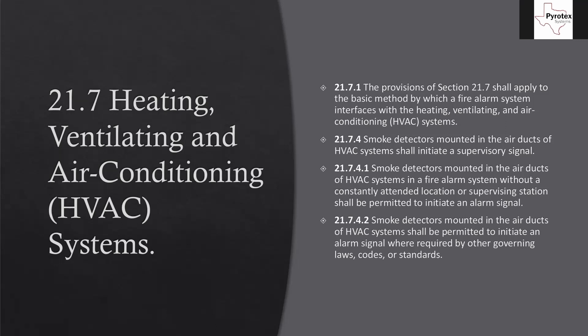The building in question is monitored by a central station over the phone line, so supervisory is still the right way to go. The second allowance: smoke detectors mounted in air ducts shall be permitted to initiate an alarm signal where required by other governing laws, codes, or standards. The local fire marshal for that building had not issued any requirement for the duct detector to initiate an alarm. For example, the city of Pearland wants all of them to be alarm signals, so it's code-compliant there, but in the city of Houston it's fine to make it a supervisory.